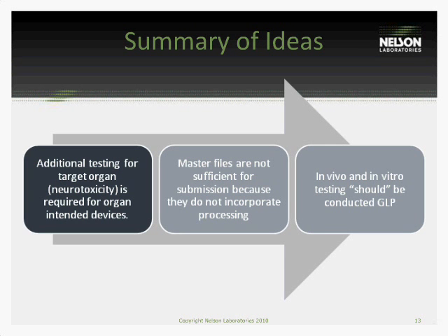So going on to more summary of ideas, one of the other things that they talked about is that if you have a certain target organ for your device, and they specifically mentioned neurotoxicity, so if your device is meant to go into the brain, then we have to do testing that's specifically targeting that organ.